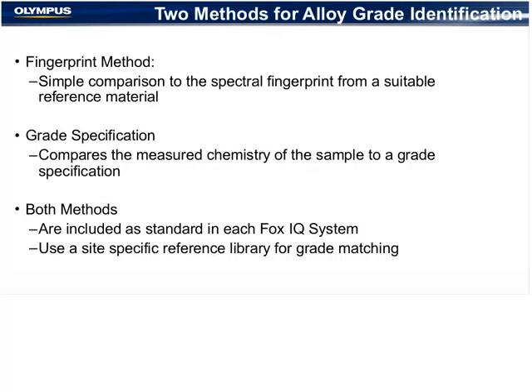Once a system is being brought into operation, there are two different options for doing alloy grade identification. The first is the fingerprint method, and it's a simple comparison to a spectral fingerprint from a suitable reference material. You want to run a 316 test, you shoot a 316 sample, make that your point of comparison and compare the other components that are running through that are that grade against that. The second type of grade ID is a grade specification where we not only capture the spectral fingerprint, but we calculate the chemistry for the sample and compare that chemistry to the grade spec. In either case, both methods are included as standard. When you get a Fox IQ system, it can run either way.